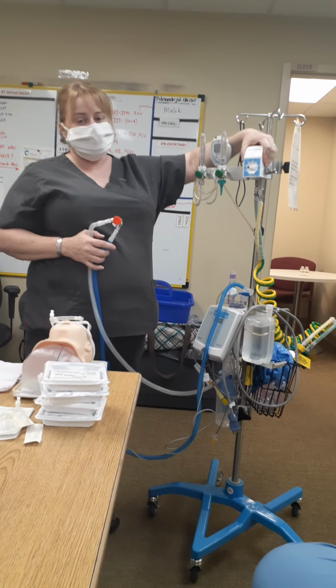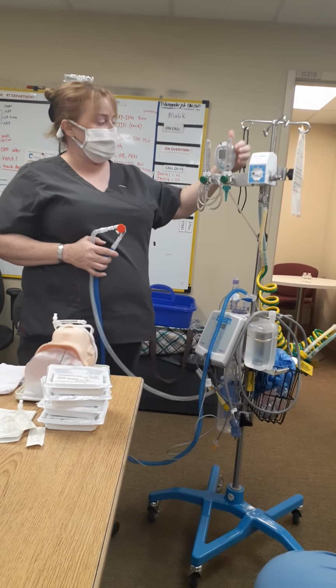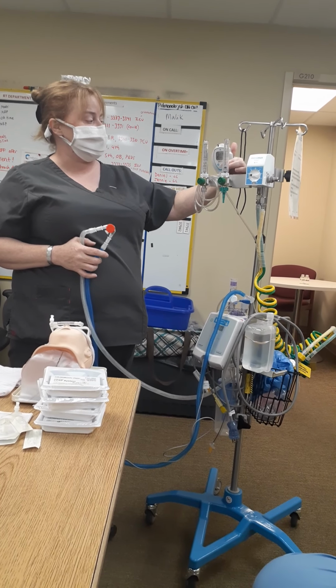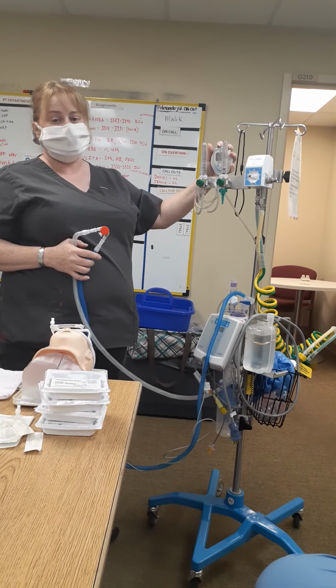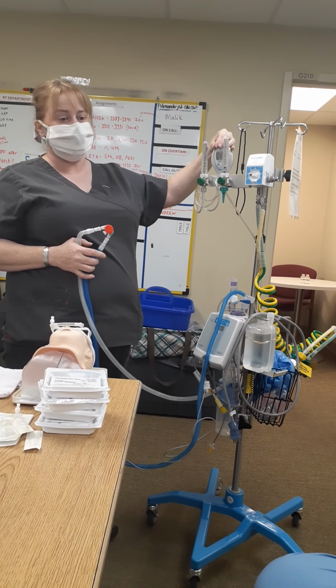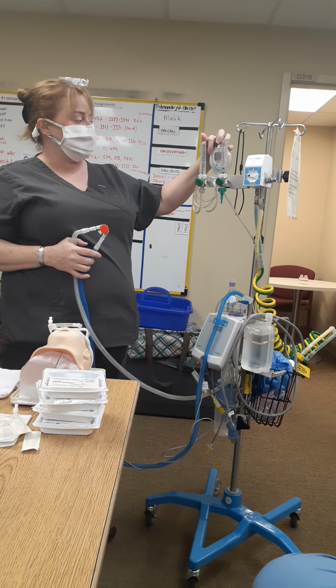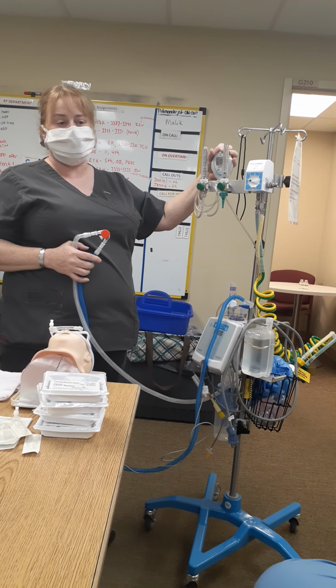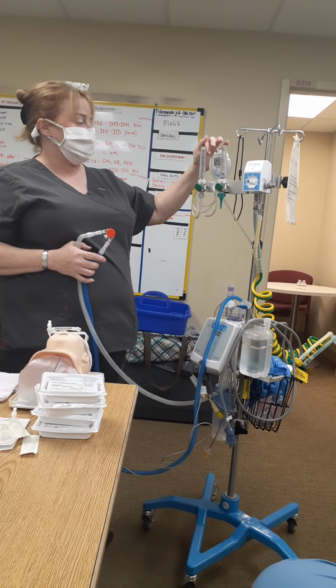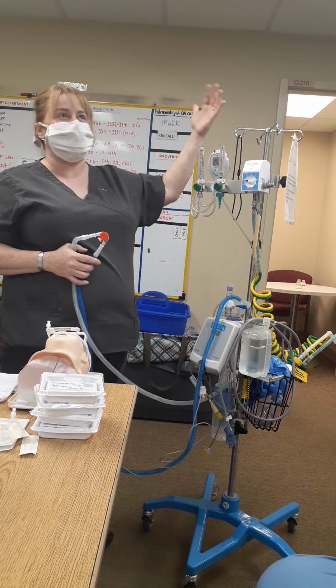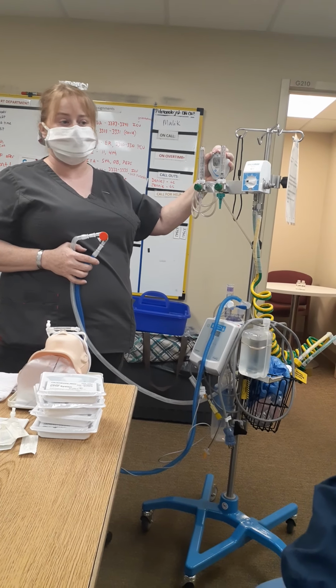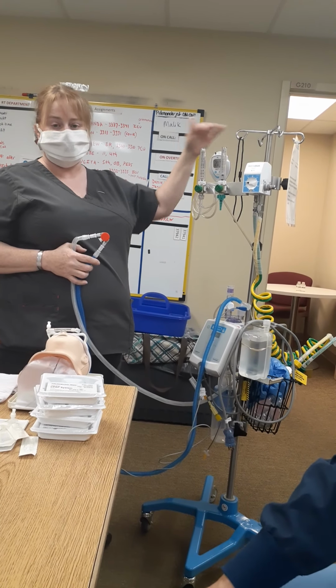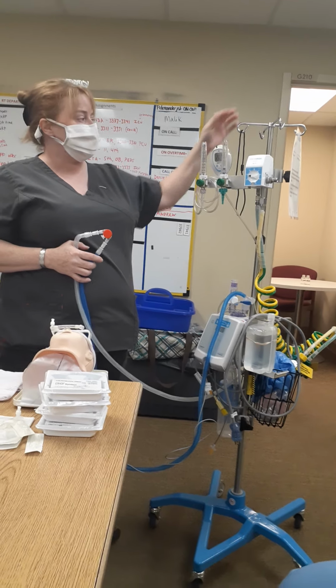Your FiO2 is adjusted by the blender, and you'll use this oxygen analyzer to determine your FiO2. This is the number we want to chart, whatever this says. If it says 20.7, I would chart 21. If it says 22.2, I would say 22. So I would just round, but chart this number.